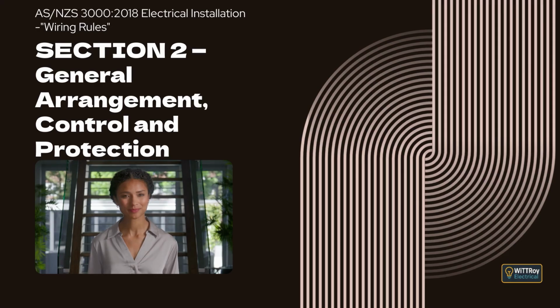Clause 2.10.5.5 Common neutral. If one neutral bar is used for more than one circuit, it must be permanently marked so that each neutral conductor can be identified correctly. Clause 2.10.5.6 Fuse. If the fuse marking does not clearly show the rating, the rating must be marked either on the fuse, on the panel, or next to it. Fuses used as a group must be arranged so their ratings are easy to compare.